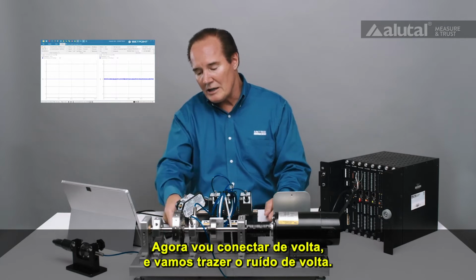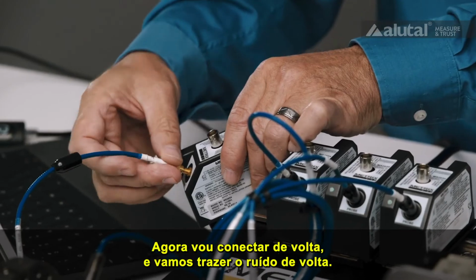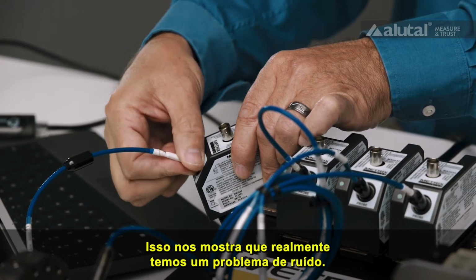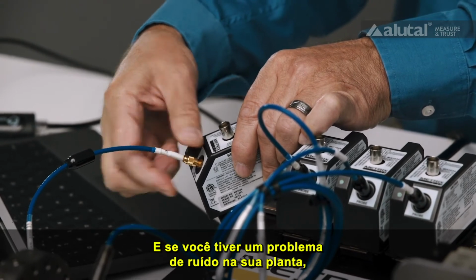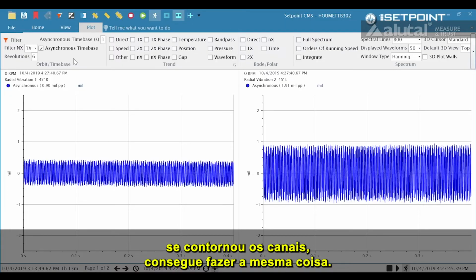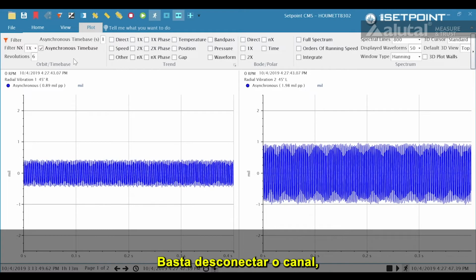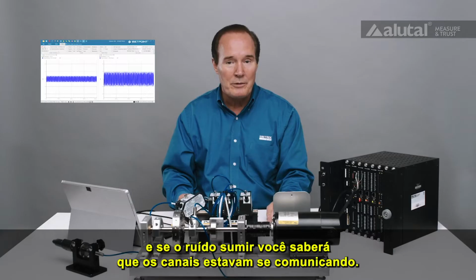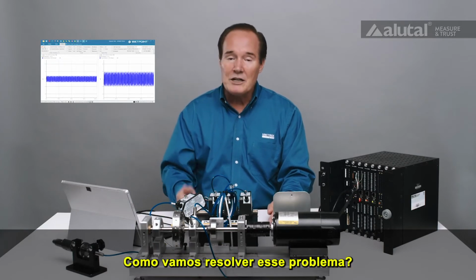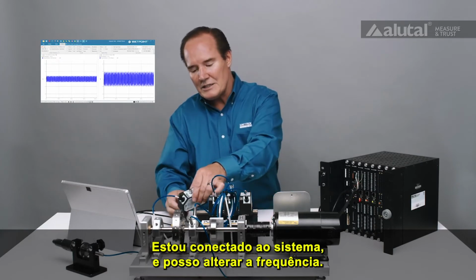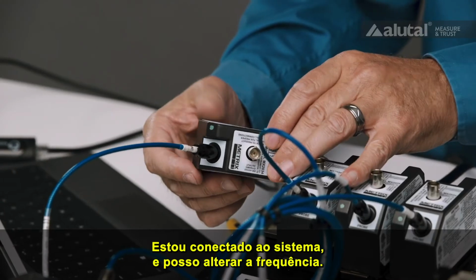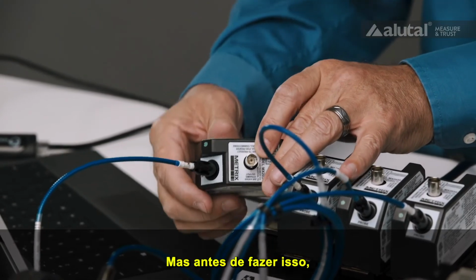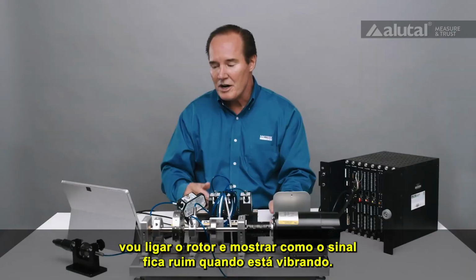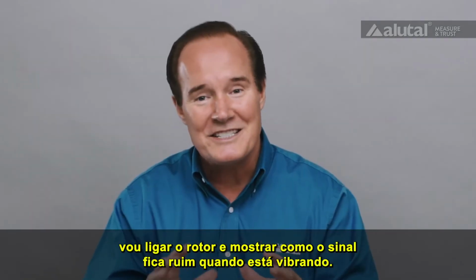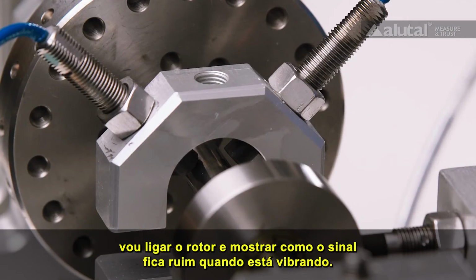Now, I'm going to go ahead and connect it back, and we're going to bring our noise back. And so that lets you know that we really do have a noise problem. And if you think you have a noise problem at your plant, as long as you've bypassed the channels, you can do the same thing. You disconnect the channel, and if your noise problem goes away, you can pretty much know that they're talking to each other. So now what are we going to do about it? Well, I'm connected to this system, and I can change its frequency. But before I do, let me go ahead and start up this rotor and let me show you what a bad signal looks like when it's vibrating.